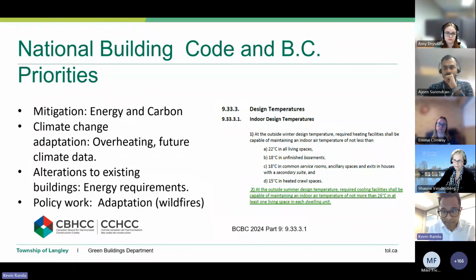What this tells us is that at outside summer design temperature, required cooling facilities shall be capable of maintaining an indoor air temperature of not more than 26 degrees in at least one living space in each dwelling unit. So if you build homes in the Township of Langley and beyond, you'll need to demonstrate that one space in that dwelling unit or home will not exceed 26 degrees at the peak of summer. There are many ways to achieve that, but it's really important that this is your obligation at building permit to demonstrate you can do it.